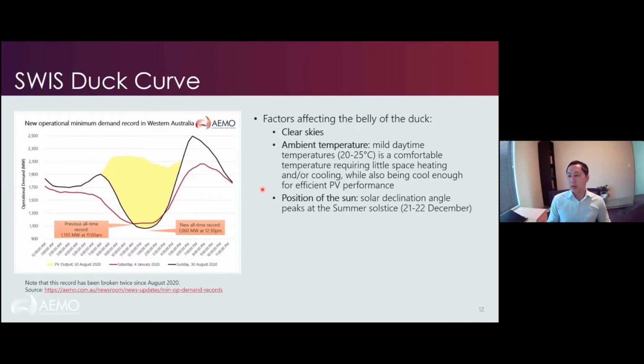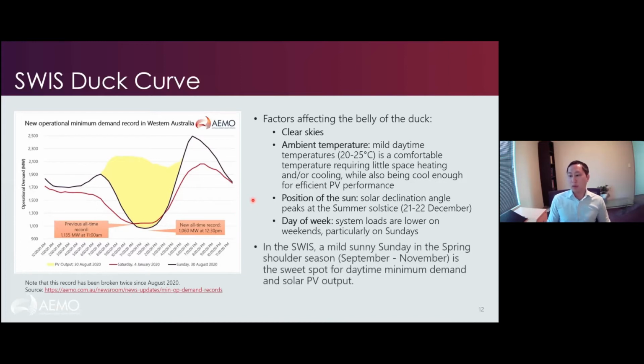The position of the sun also matters - as you get closer to the summer solstice, you get a better solar declination angle and better PV output. The day of the week matters too, since system load is lower on weekends, so the belly of the duck gets lower on a Sunday. What we normally see is a mild sunny Sunday in spring, so between September and October is really the sweet spot, when all these factors come into play.